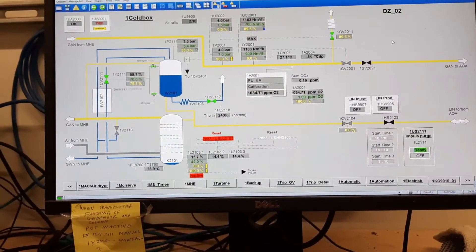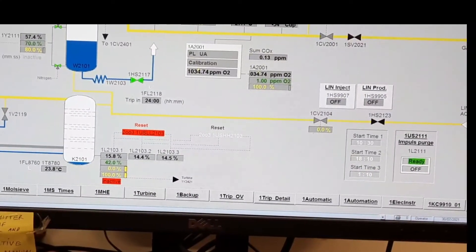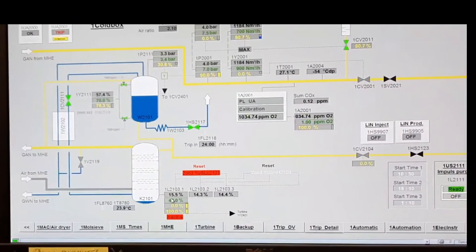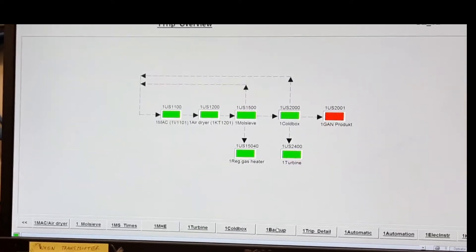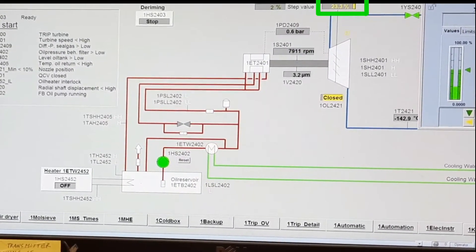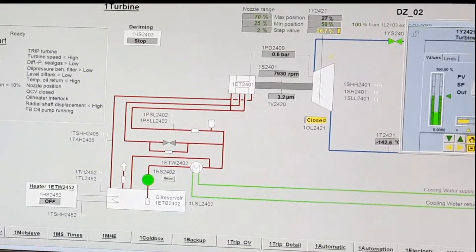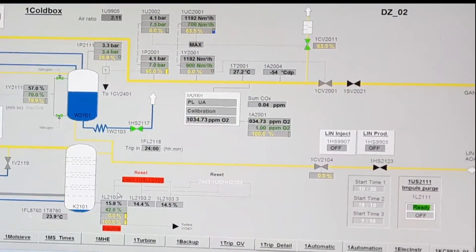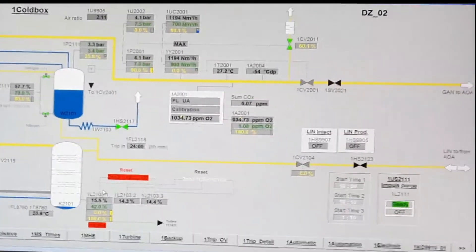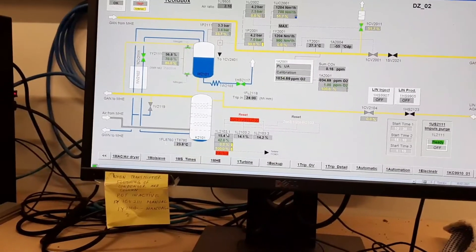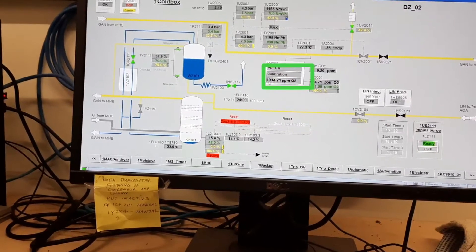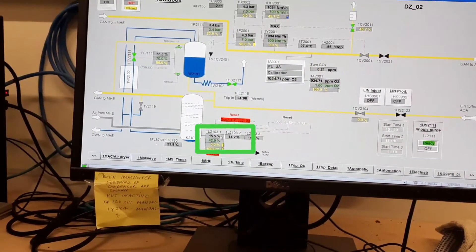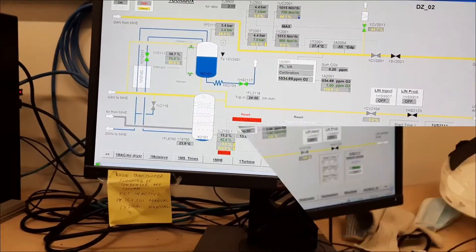Now we need to wait for the column level to increase. After the column level increases, we will restart the turbine operation. The turbine is currently at 25 percent. The level can increase, no problem. You can increase the turbine output to about 56 percent. We will wait for the oxygen purity to stabilize and the level to rise.